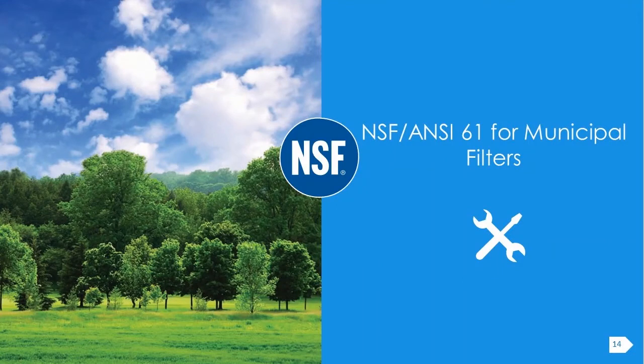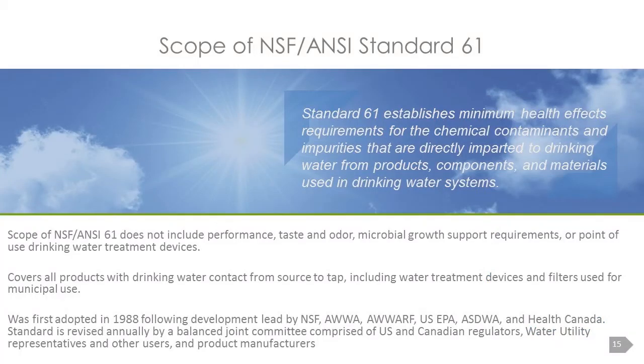Now I'm going to dig in a little deeper to NSF ANSI 61, especially as it relates to municipal filters. The scope of NSF 61 is that it establishes minimum health effects requirements for chemical contaminants and impurities that are directly imparted to drinking water from products, components, and materials used in drinking water systems. The scope does not include performance, taste and odor, microbial growth support requirements, or point-of-use water drinking treatment devices. Basically, the scope covers all products that could have contact with drinking water, anywhere from the source to the tap, including water treatment devices and filters used for municipal use.